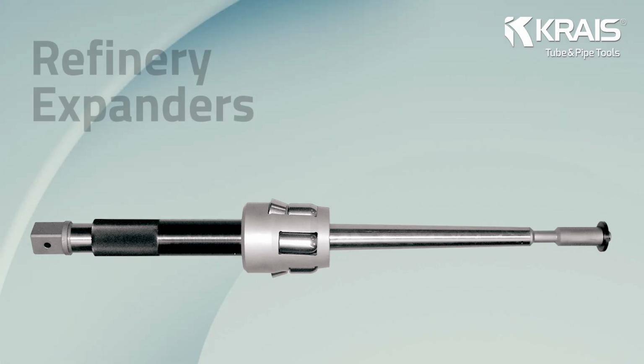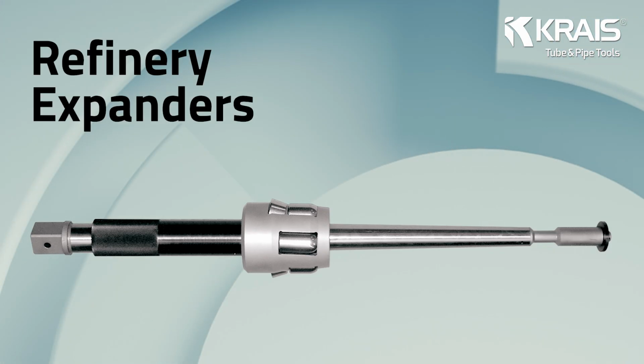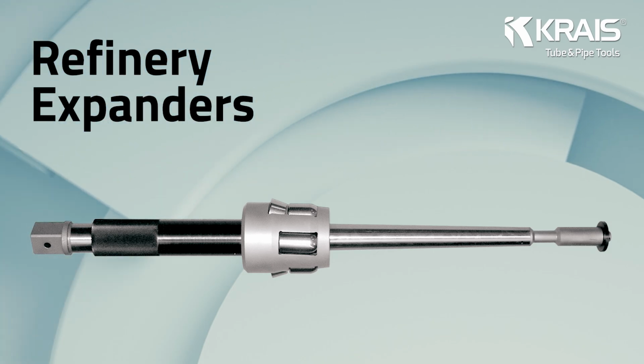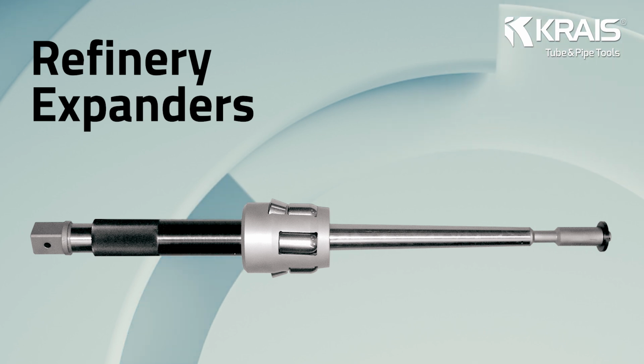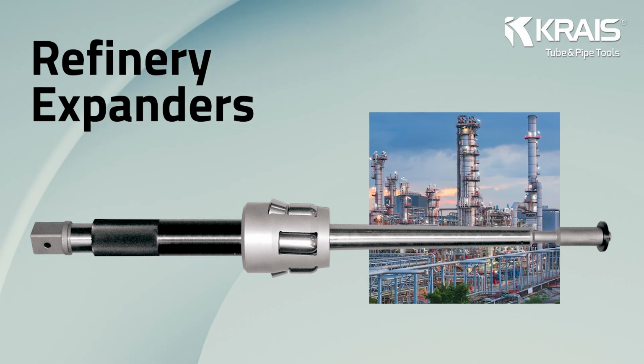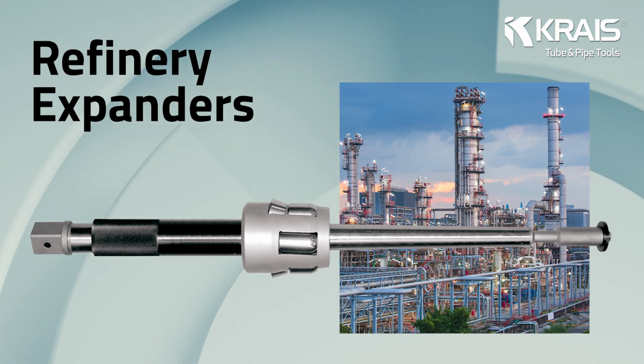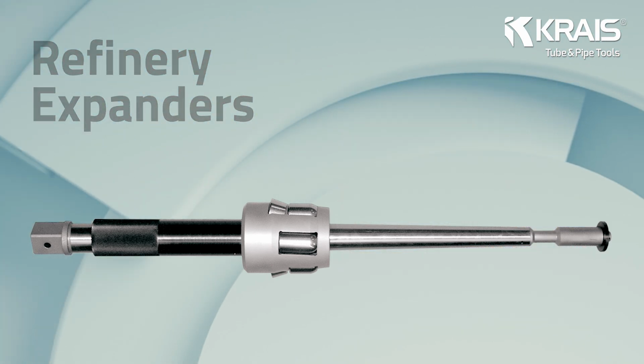KRAIS refinery expanders are intended for large, heavy wall tubes in heater and furnace tube seats, including cracking furnace in oil refineries. Depending on configuration, they can perform straight expansion or expansion with flaring, and selection is driven by seat geometry and the applicable maintenance specification.